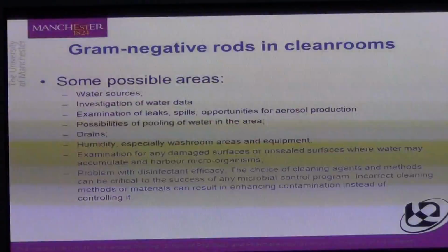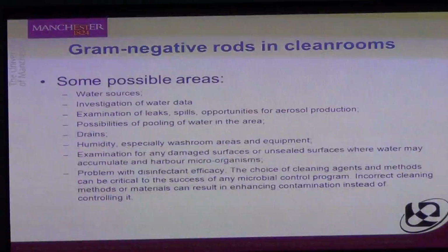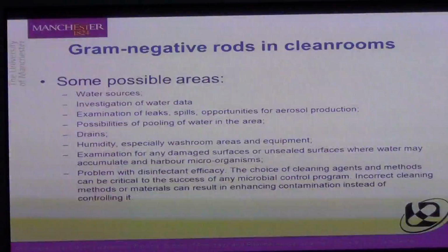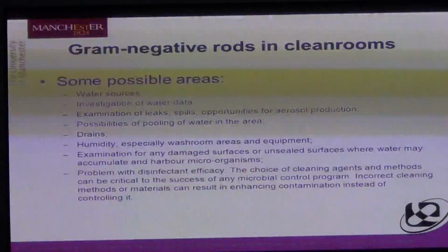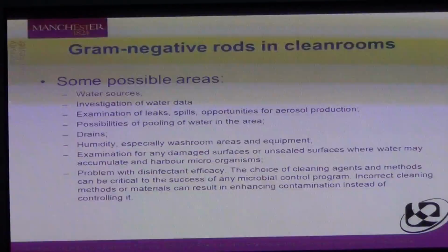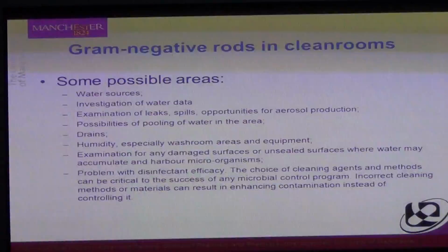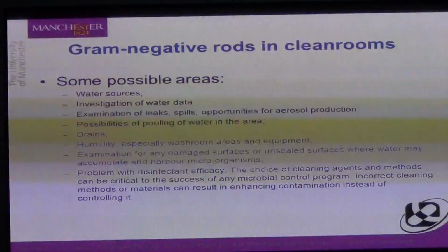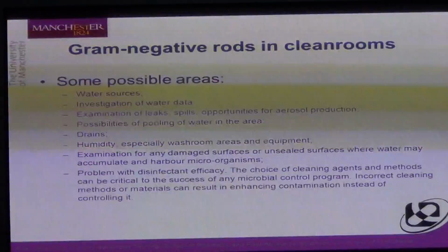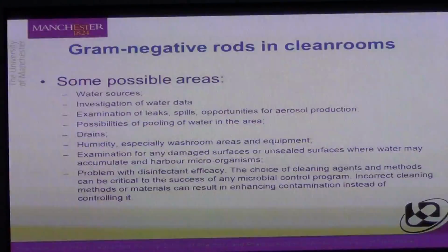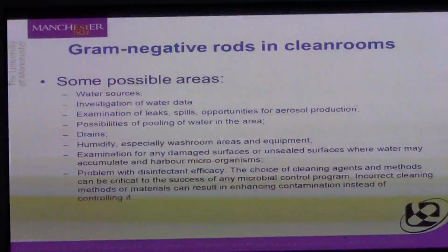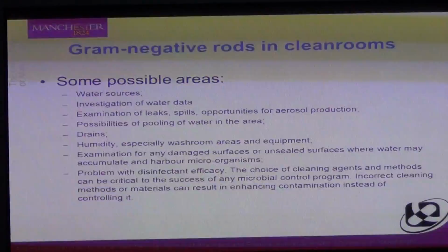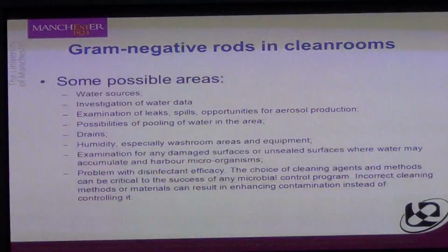Are there pools of water? Are there risks from drains? Are you in a high humid area? Do you want to look for any damaged surfaces or unsealed surfaces where water may accumulate and you may have microorganisms harbouring? You also want to have a look at whether your disinfectants are working properly, and incorrect cleaning methods may also enhance contamination. So these are some of my thoughts. I'm sure you found some equally good ideas of your own, and this is just an example of some of the things that you encounter as you work through the module.